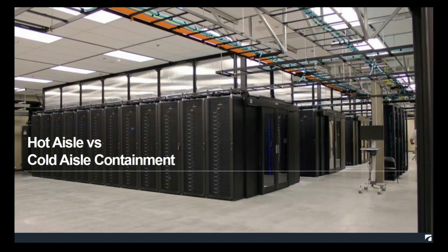So, hot aisle versus cold aisle containment. We talked a little bit about that, and people tend to have a preference of one over the other, potentially depending on their experience. My opinion is that cold aisle containment tends to be best suited for retrofits. Say you already have a raised floor environment, you want to retain that, you want to do some containment, but you can't really redo your entire HVAC system. Doing something like Steve showed with the lid over the cold aisle and doors at the end of the cold aisle may be a very good solution for that.